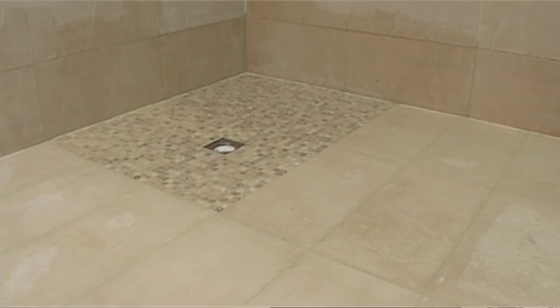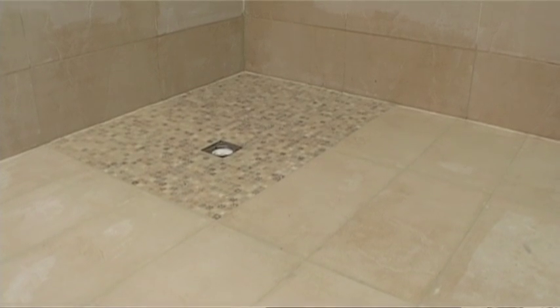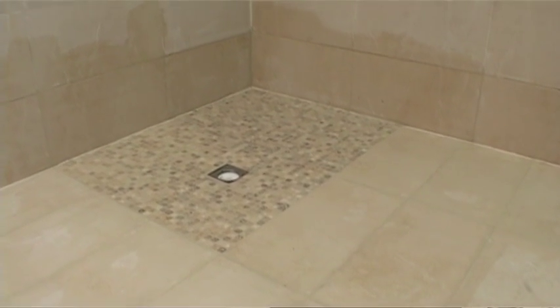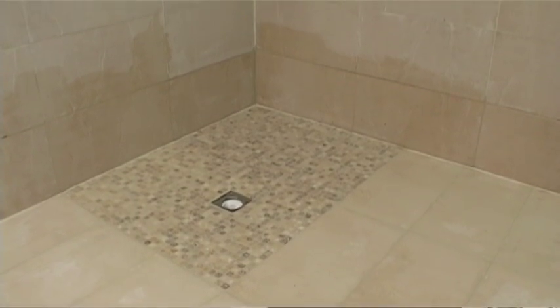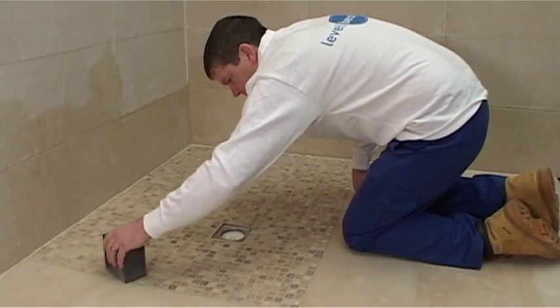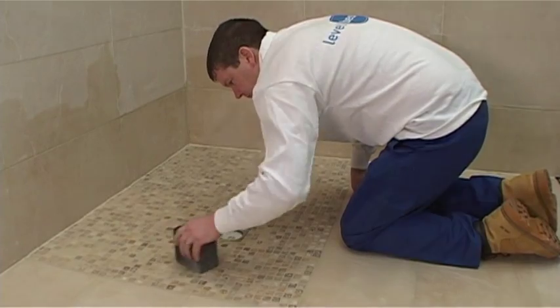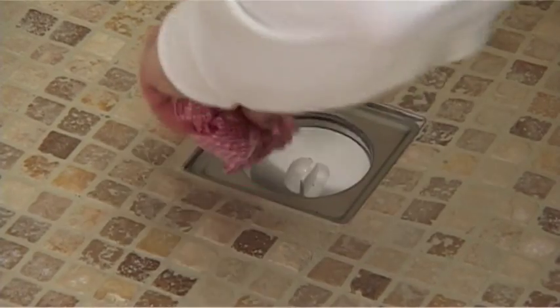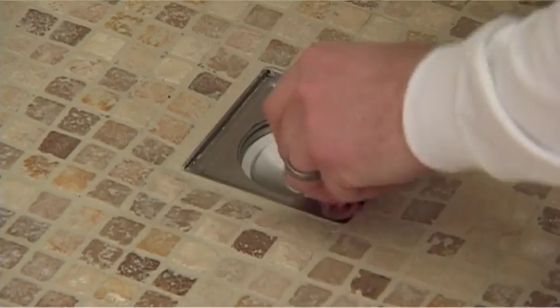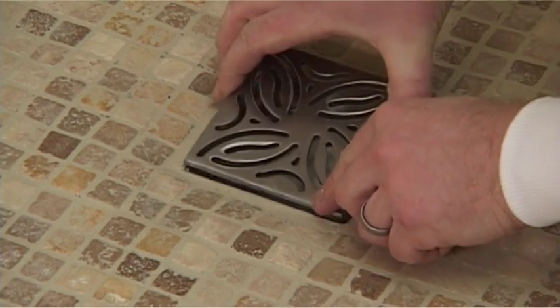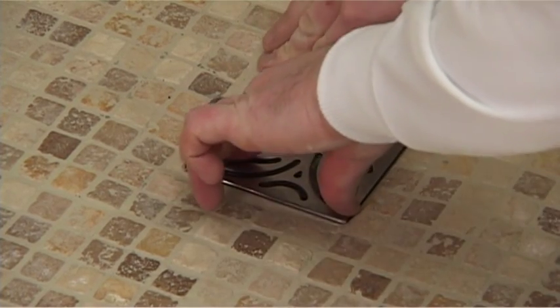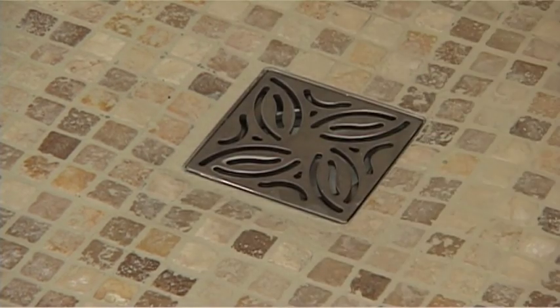You must now leave the installation unheated for a minimum of 7 days to allow the floor to completely dry and consolidate. During this time, it is very likely the shower screens will be installed, so these multimeter tests must be repeated prior to final commissioning. You can now follow the detailed setup and commissioning details supplied with the individual heater mat.